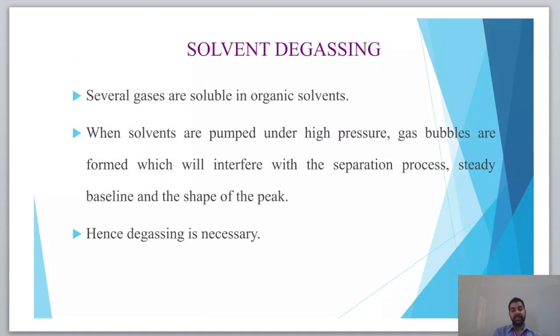Next, solvent degassing. Several gases are soluble in organic solvent. When solvents are pumped under high pressure, gas bubbles are formed, which will interfere with the separation process. As I have already explained, they affect a steady baseline and the shape of the peak. If there are gas bubbles, they will interfere with the flow rate of the solvent. So we are going to get interference with the separation process in HPLC.